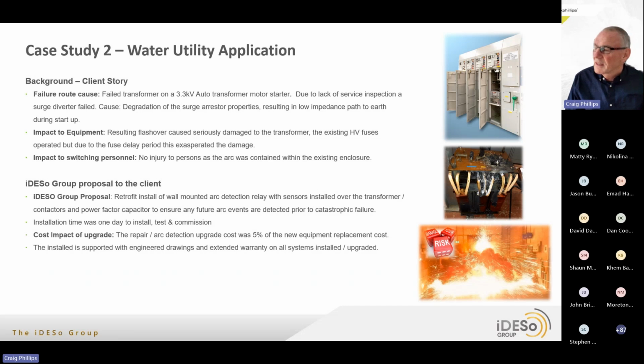Surge arrestors have no real indication when they're failing. They're there to direct any surge down to earth, and they do degrade if they're continually being stressed. The typical maintenance regime is to change them every 5 years or inspect them during maintenance. This hadn't been done, resulting in a low impedance path to earth during startup. The impact on the equipment: there was a flashover causing significant damage to the transformer. You can see that in the middle picture to the right, and also to the enclosure and to other equipment.